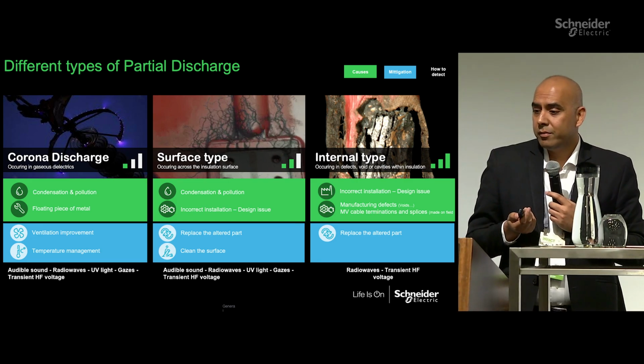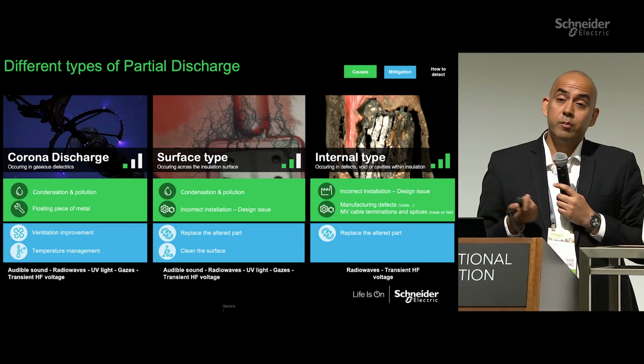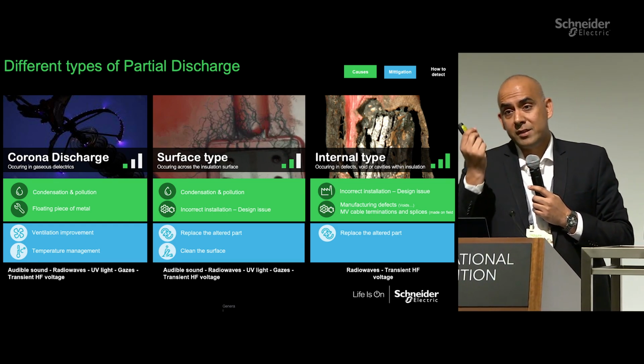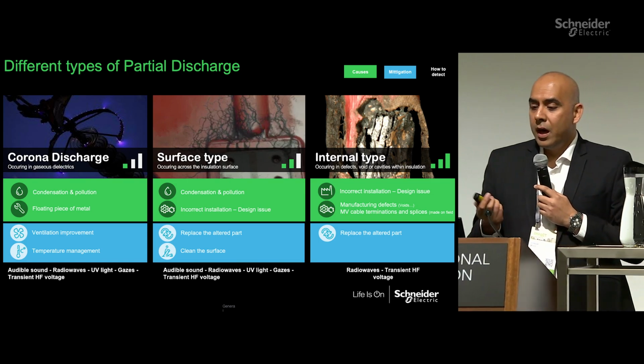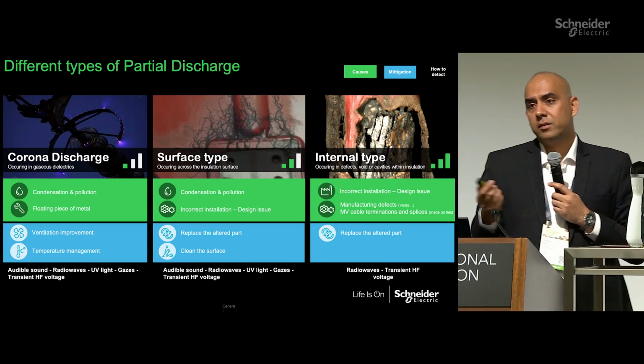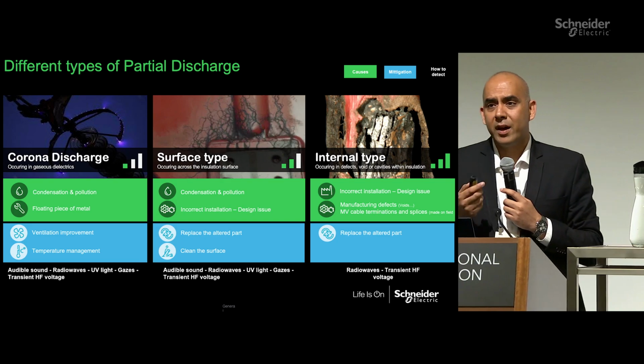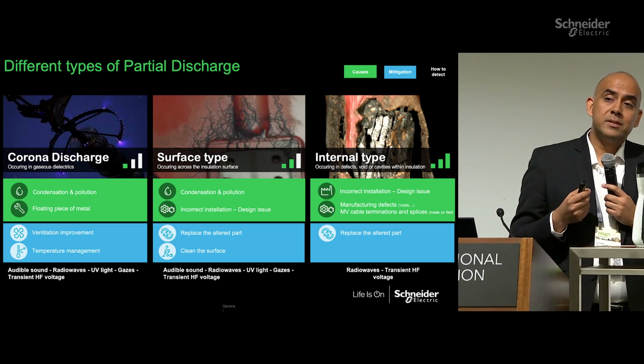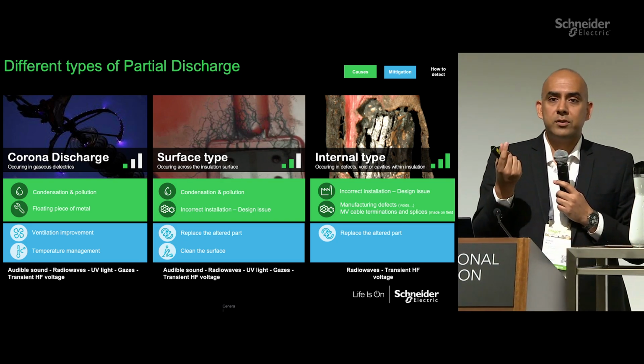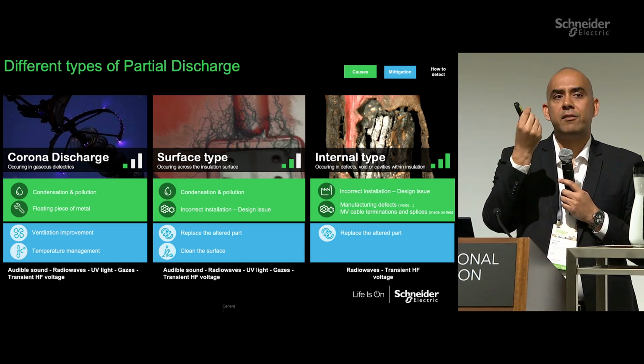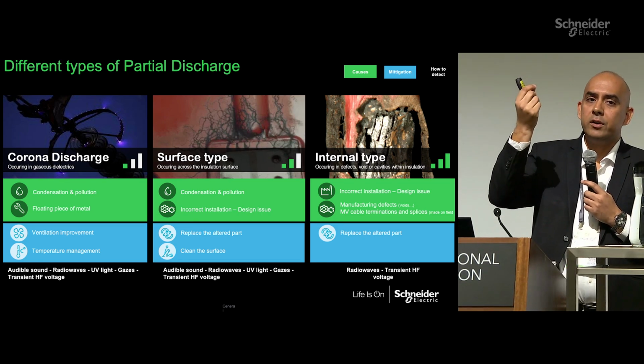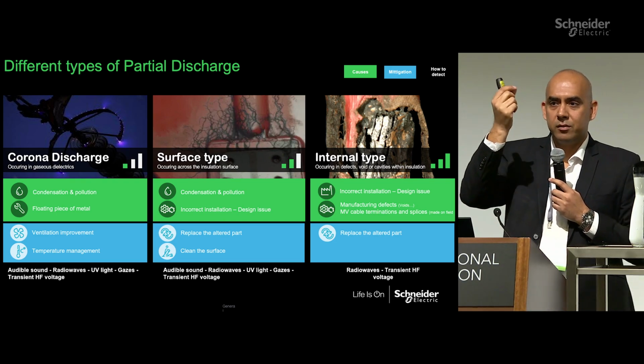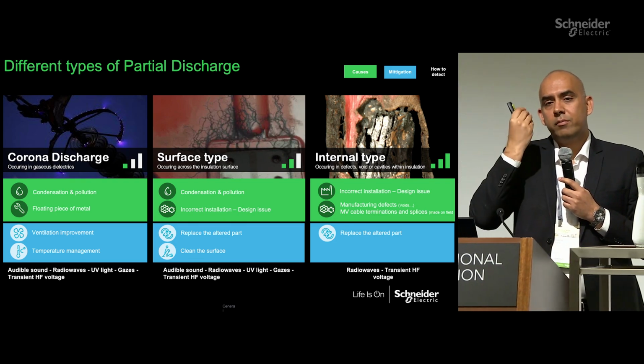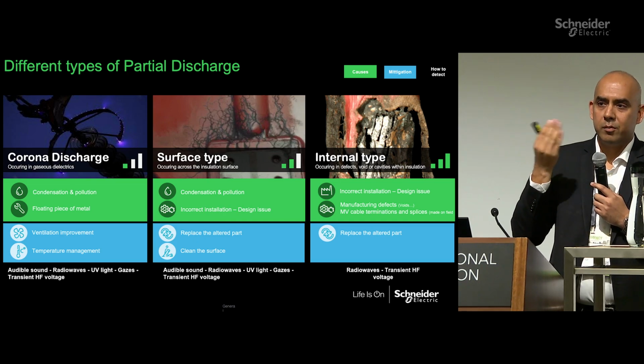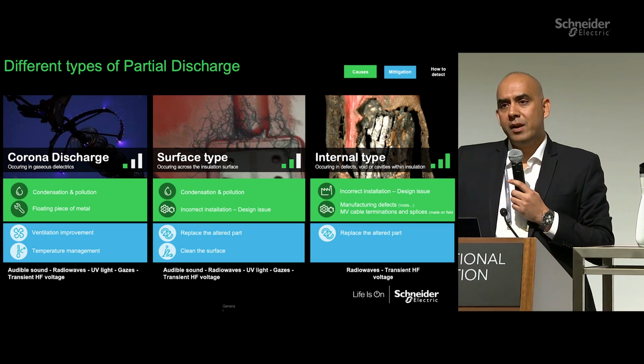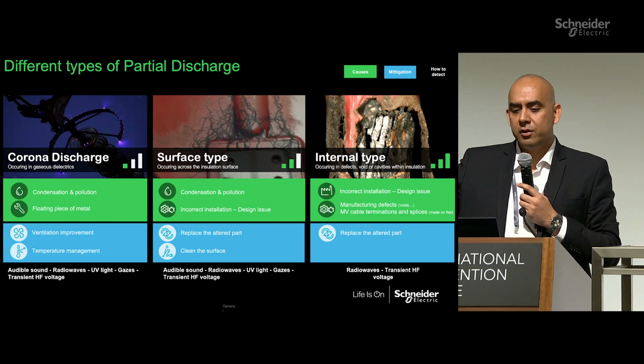And the causes could be condensation, improper environment. It could be some materials which are floating in the air. And how you can mitigate is you can probably work on the ventilation, you can work on the temperature management, etc. of the systems. And many times the sign of a partial discharge is the acoustic, the sound. If you see an electrical system, you would have observed in the video there is a hissing sound which was coming in. Okay? So if you could hear that sound, you could see that something is going wrong, probably. And sometimes it's at a consistent level, and it can increase gradually if the insulation is weakening.